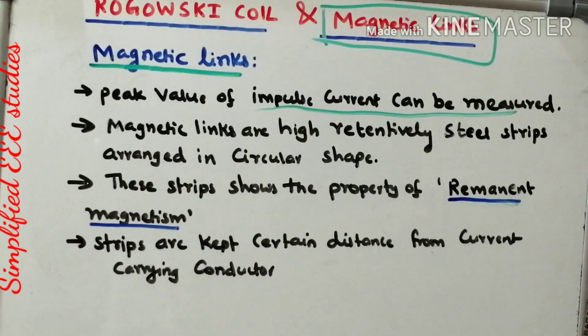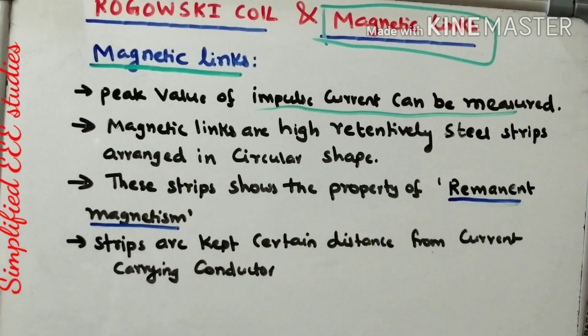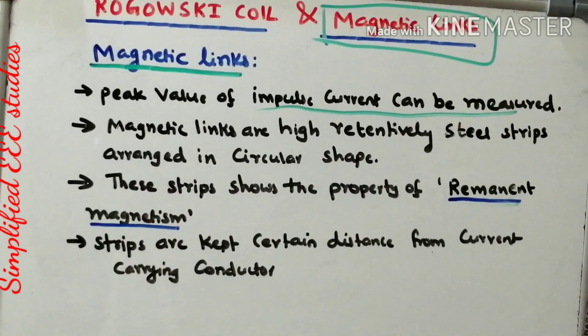In this session we have discussed the Rogowski coil — a toroid-shaped coil operating on Faraday's laws of electromagnetic induction. With an integrator, its output voltage is directly proportional to the current passing through the conductor. We also discussed magnetic links, which work on the principle of remanent magnetism to measure the peak value of impulse current. Thank you very much for watching. If you found this channel useful, please subscribe.